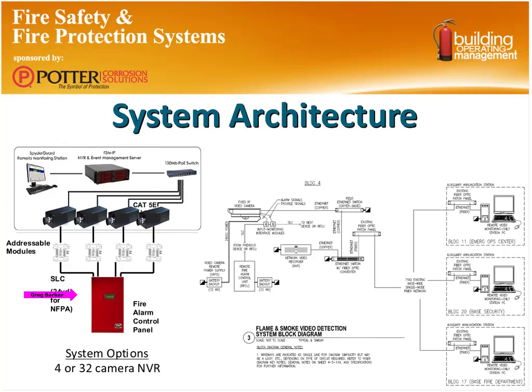And people say, well, why do we have to have both? I can get my information from the video architecture by using the analytics built in. Why do I need the fire alarm piece? To be truly UL tested and meet the intent of NFPA 72, the systems have to, one, be able to be battery backed up, and two, be fail-safe. Otherwise, if part of the system fails, we need to know that. The only way to do that is to have onboard analytics within the camera body, and monitor contacts on the back of each camera with a traditional fire alarm input module. That becomes our UL-listed, NFPA-compliant fire alarm input device.